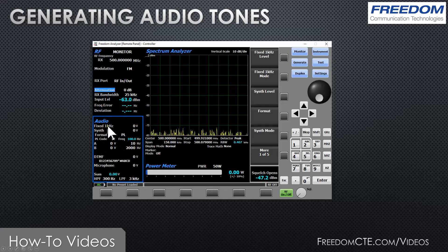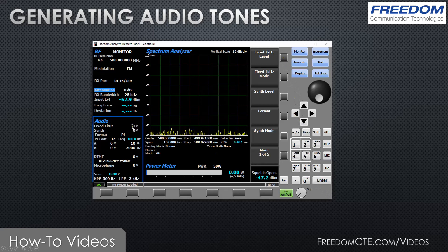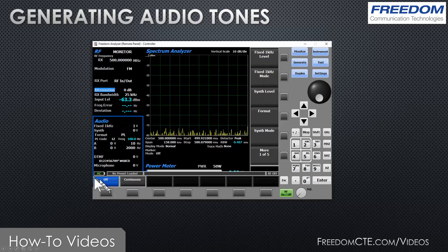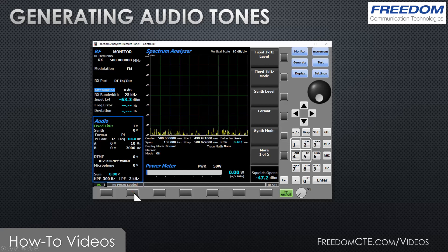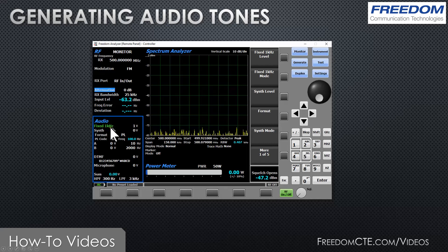If I would like to send an audio signal from the mod out port — let's say I want to configure a fixed one kilohertz tone — using the vertical soft keys, fixed one kilohertz level, let's say I want to put out a one volt peak signal. That has set the level but has not turned it on. In order to turn it on, at fixed one kilohertz mode, I can set it — as you can see at the bottom it's off — I can turn it to continuous. Once I've done that, on the R8100 it turns green to let me know that it's turned on. This is now available at the mod out port, so you could feed it into the audio input on a radio to have the radio modulate its carrier.